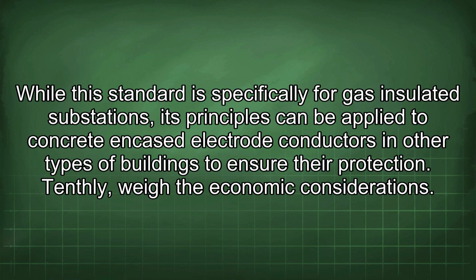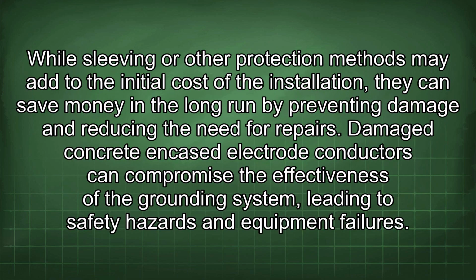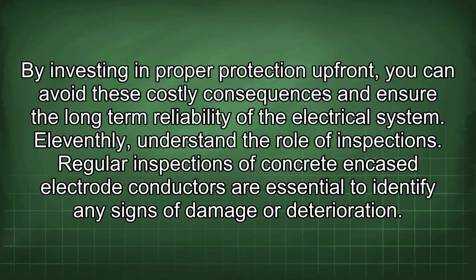Tenthly, weigh the economic considerations. While sleeving or other protection methods may add to the initial cost of the installation, they can save money in the long run by preventing damage and reducing the need for repairs. Damaged concrete encased electrode conductors can compromise the effectiveness of the grounding system, leading to safety hazards and equipment failures. By investing in proper protection upfront, you can avoid these costly consequences and ensure the long-term reliability of the electrical system.